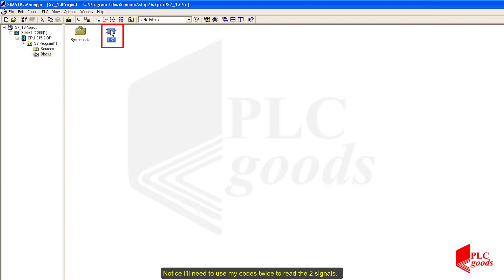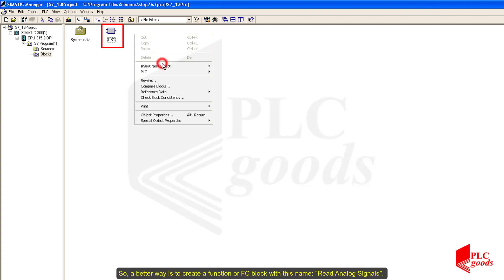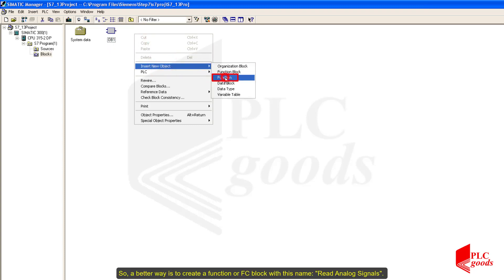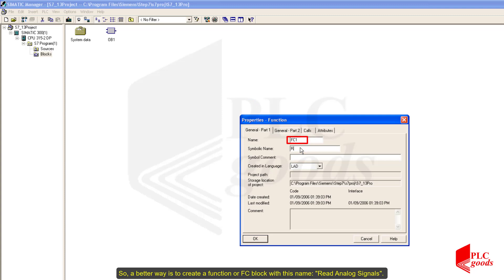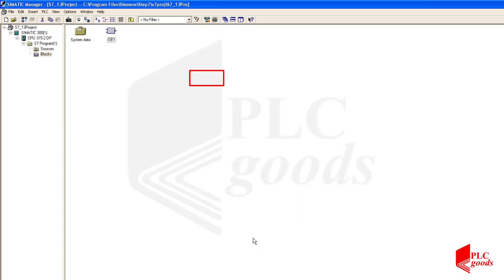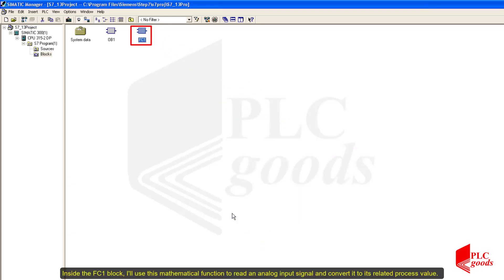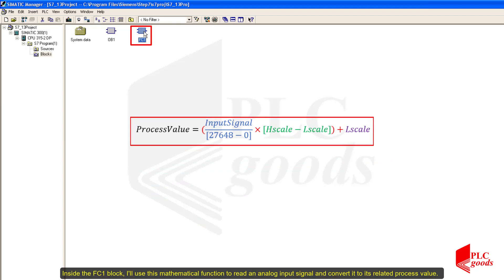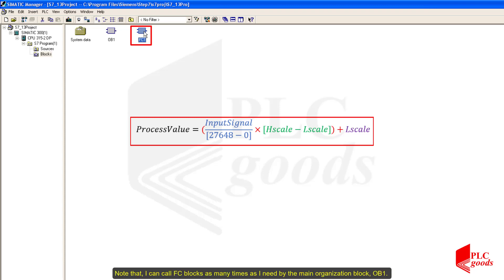I'll need to use my code twice to read the two signals, so a better way is to create a function, or FC block, with the name 'read analog signals'. Inside the FC block I'll use a mathematical function to read an analog input signal and convert it to its related process value. Note that I can call FC blocks as many times as I need from the main organization block OB1.